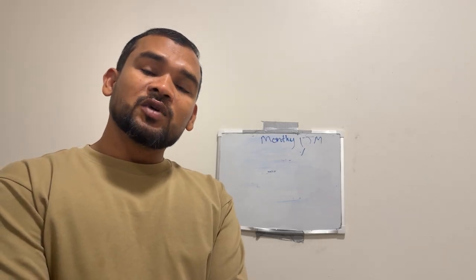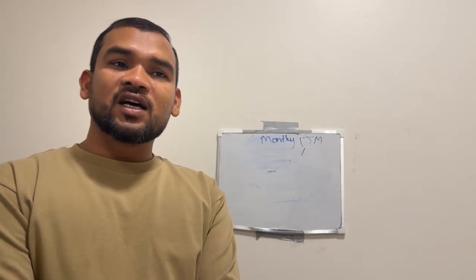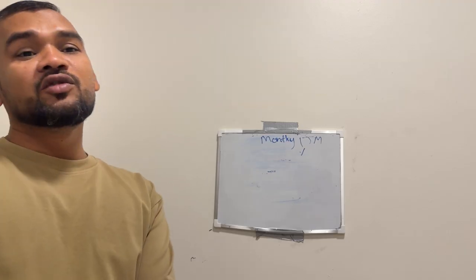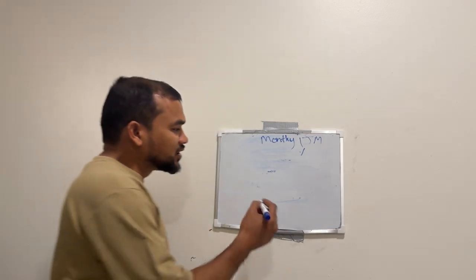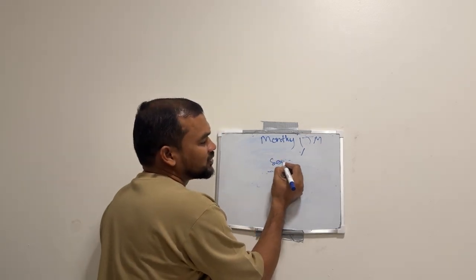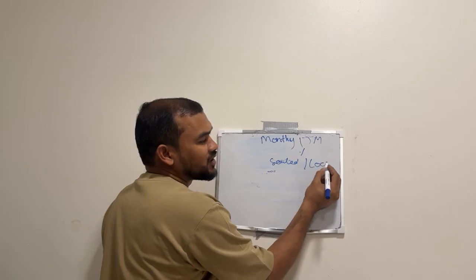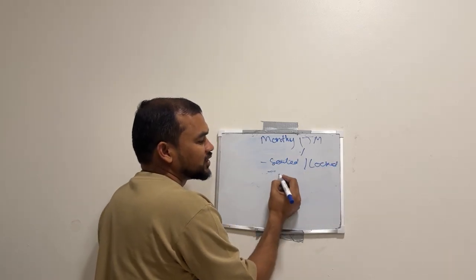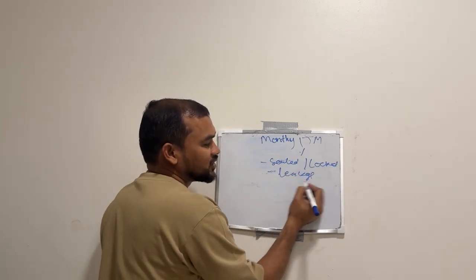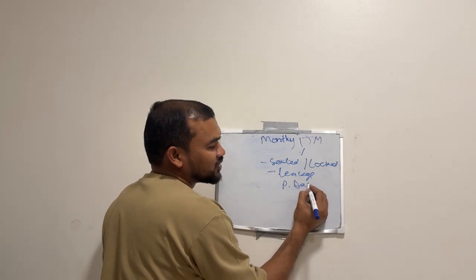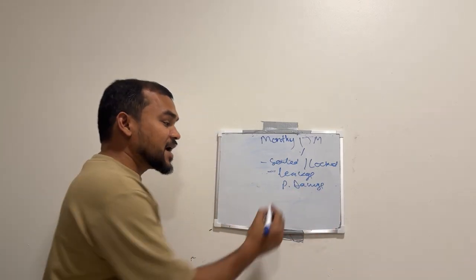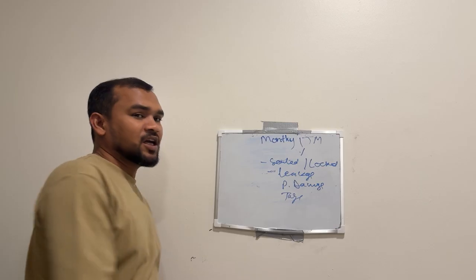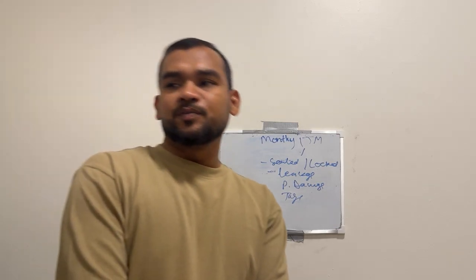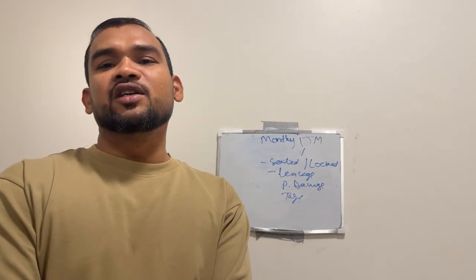If it is not supervised with the fire alarm system, in the inspection we are checking that the valve is in the correct position. We have to check accessibility. We have to check whether the valve is sealed, locked, or supervised. We have to check for any leakage, for any physical damage, and that the proper approved tags are there. We have to check on a monthly basis.